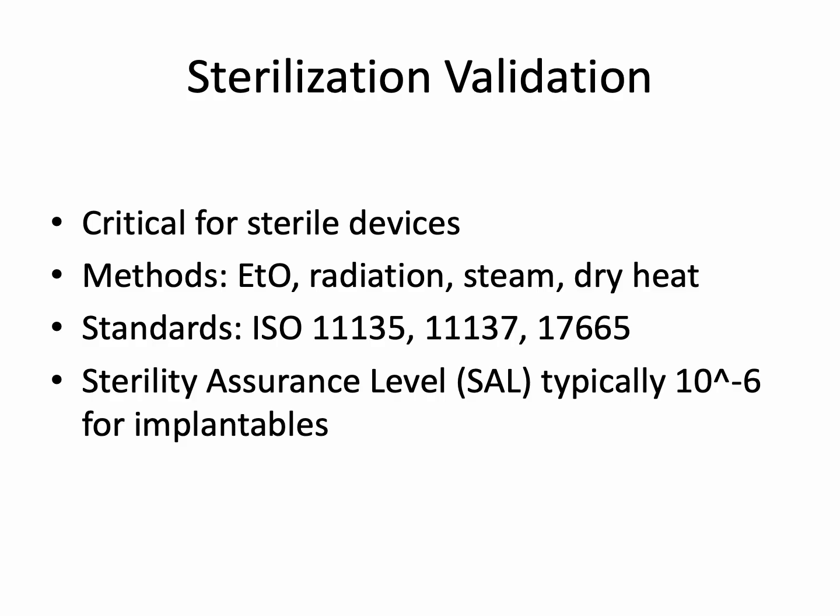Sterility assurance level, SAL, is typically 10 to the power of -6 for implantable devices, representing a 1 in a million chance of a viable microorganism surviving the sterilization process. Proper validation demonstrates compliance with international standards and regulatory expectations, reducing risk to patients and ensuring market acceptance.